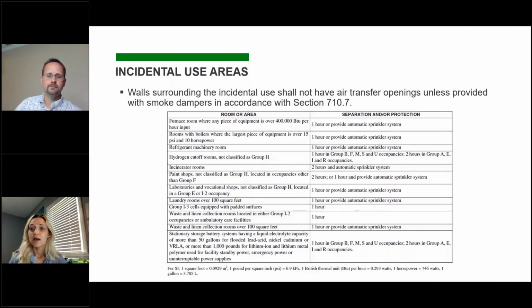And there are a lot of items in this table that are specific to healthcare occupancy. In the IBC, I-2, Institutional 2, is what's considered healthcare. So we can see there are specific requirements for laboratories in healthcare, laundry rooms, etc. And this table helps identify a lot of the times when hazardous rooms need to be protected in some way. So just remember that if we are sprinklered, you do not have to provide the 1 hour fire rating if it says 1 hour or sprinkler system, but we still need to protect the room with a smoke partition and then protect it accordingly on our mechanical drawings.